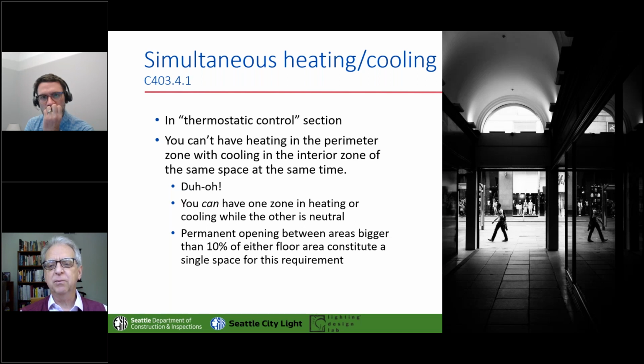You see this opening here between one space in a building and another larger space. If that opening is bigger than 10% of the floor area on either side of the opening, and it's a permanent thing, not closed by doors, then that's a single space as far as the simultaneous heating and cooling rule goes.